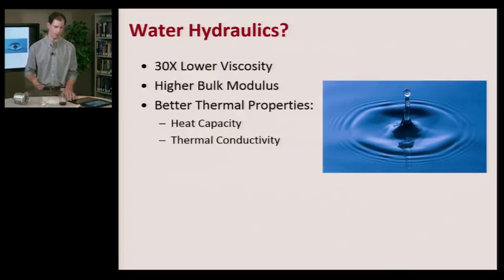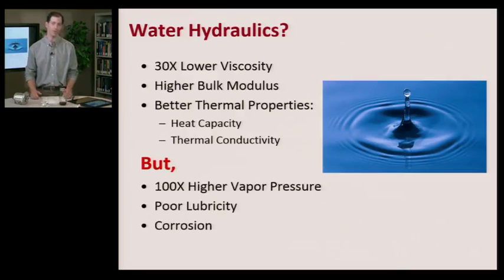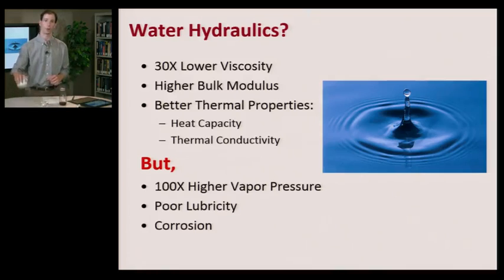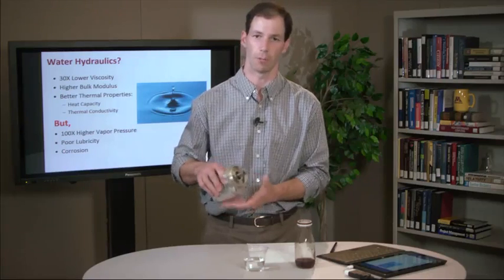That said there has to be a but, and the but is first it has a hundred times higher vapor pressure than a mineral based oil. So this means that water-based hydraulic systems are very prone to cavitation at the inlet to a pump or other locations where we're seeing a drop in pressure. And this is especially true as you start to raise the temperature of the water.